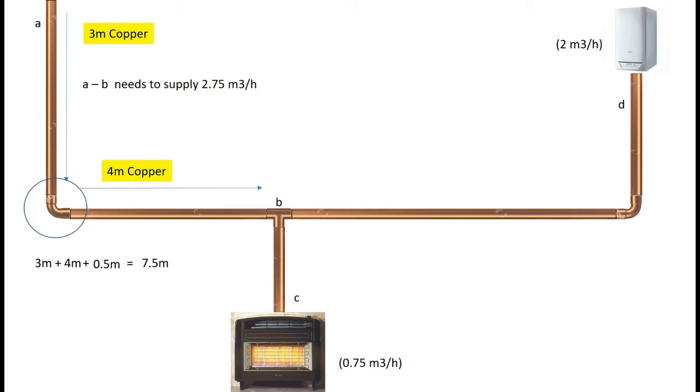Just take my word for it. All you do is you multiply the length of the pipe that you've got by the amount of appliances on the system. In this case, you multiply the length by 2. 7.5 times 2 is 15 meters.